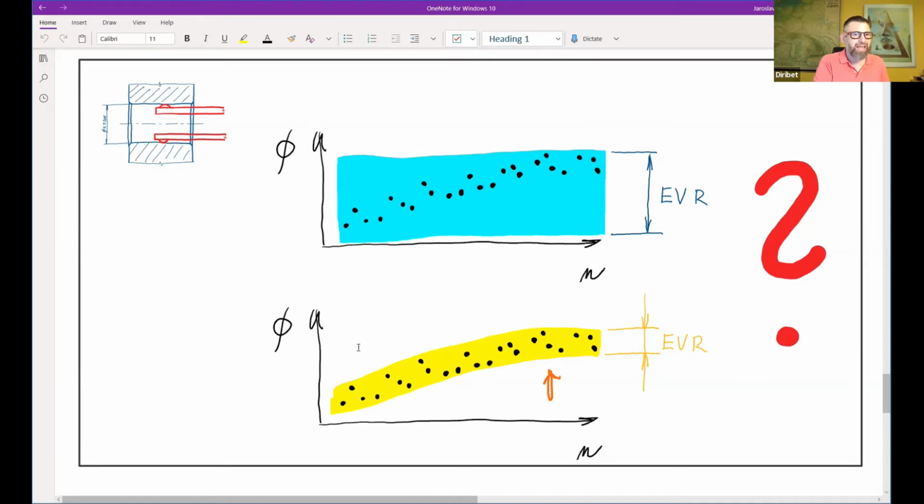In this case, we are in fact putting in a part which has a different dimension than it had before. So it is completely all right if the measurement system shows a different dimension in the end. It's not a problem of the measurement system. It actually shows that the measurement system is doing something. And that is a very good reason to account for that and not to penalize the measurement system with such a broad estimate of equipment variation uncertainty.